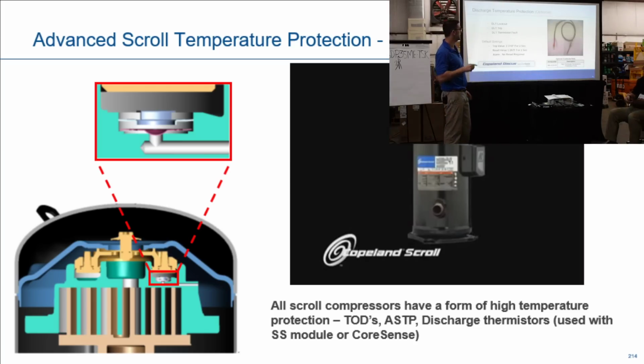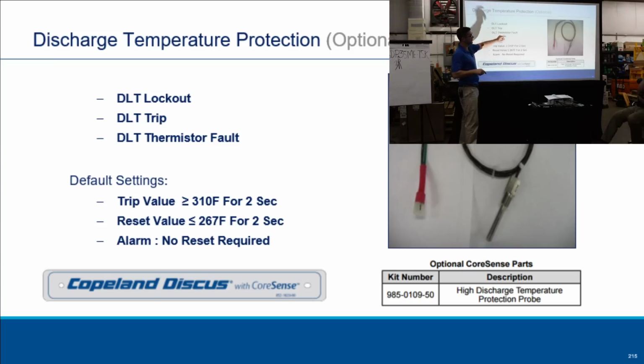I'm going to skip the video because I've got quite a few more slides to go through. Optional for our CoreSense model: if you work with any of our semi-hermetic compressors, you're going to have a CoreSense on the new ones. That's the way they come. Same with the old. If you're replacing it now with a service compressor, you won't have it on the service compressor, only on the OEM models. So you'll have to take the CoreSense off the one that's on your system and put it on your service compressor, just like the old Sentronics.